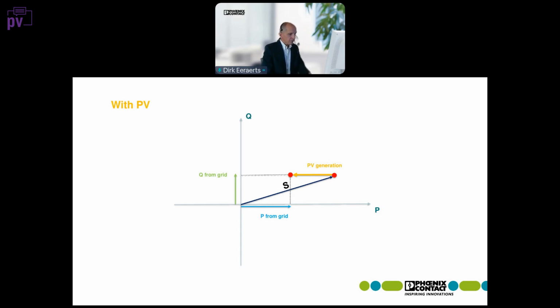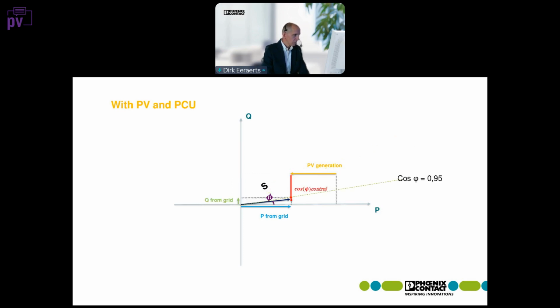So he's quite happy. But then after a while, he gets his bill and he sees that now his operating point is really on the graph above, but it means that the cosine phi is lower than 0.85. And so he takes the same amount of reactive power from the grid if there is no control, but he pays a higher price for it. That is something that I've seen many times. It creates conflicts. The good thing is if you add a power control unit, you can actually bring this point down and you can make the situation better than what it was before the PV was added.